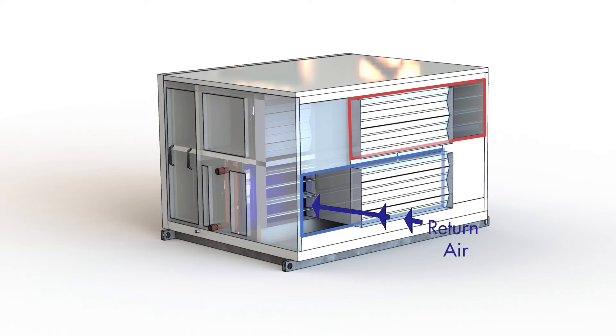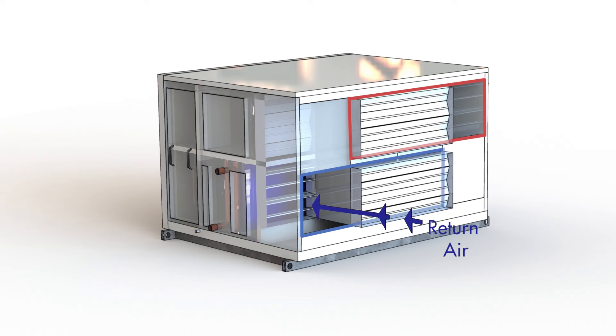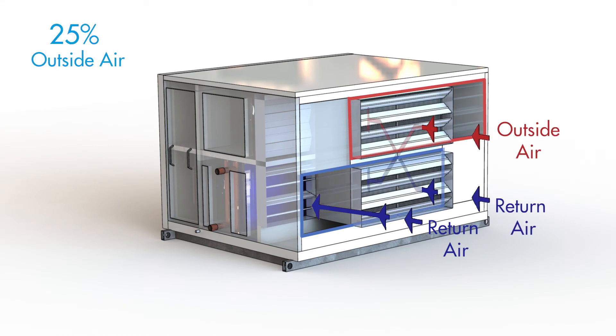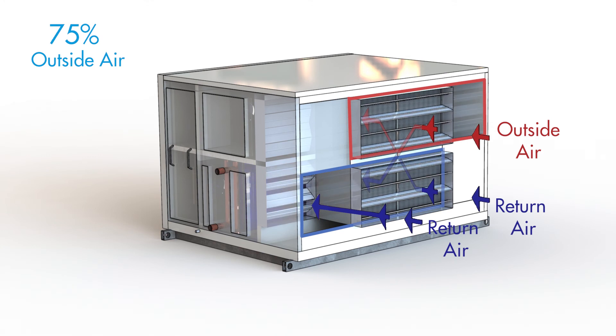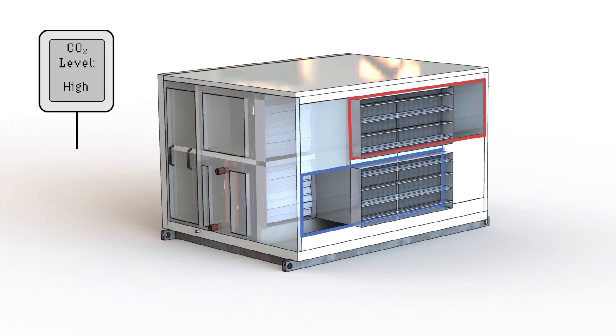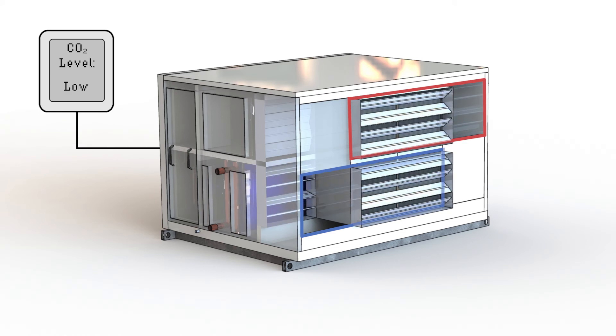For example, for an early morning warm-up cycle when there is no one inside the space, the unit might run in full recirculation, meaning that the return air bypass damper will be fully open, while the heat exchanger damper will be fully closed. But as the indoor space becomes occupied, the heat exchanger and return air bypass dampers can open and close inversely to each other on an analogue scale. This allows any fresh air proportion to be achieved, and often this is driven by CO2 readings from the space, which provides demand controlled ventilation.